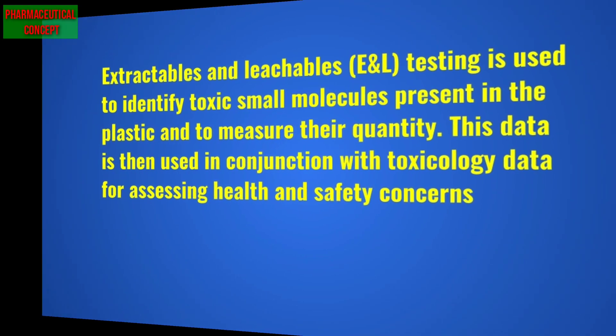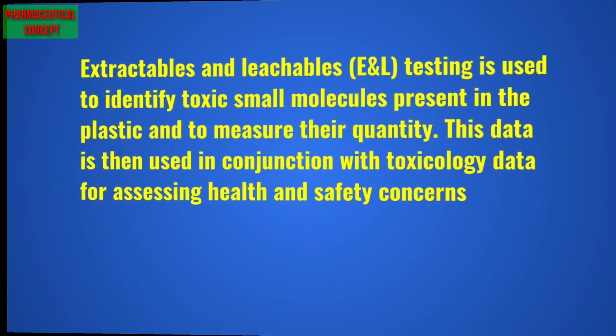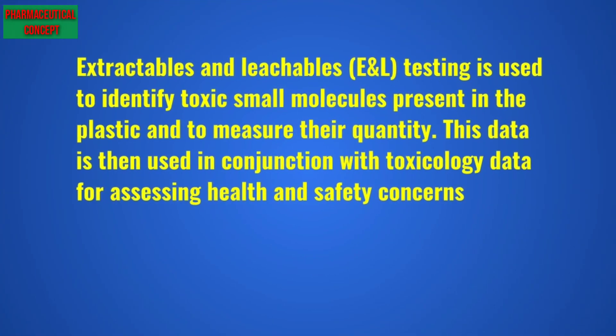Extractable and Leachable (E and L) testing is used to identify toxic small molecules present in plastics and to measure their quantity. This data is then used in conjunction with toxicology data for assessing health and safety concerns.